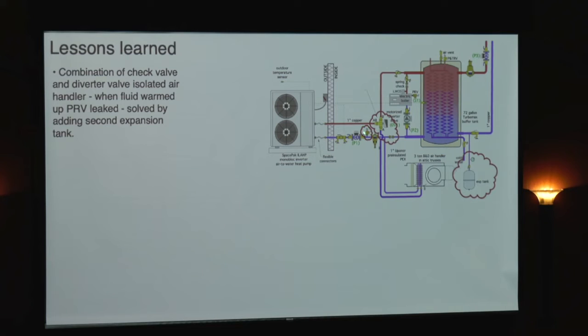The relief valve is here. And what happened? Well, we sealed off all communication, so to speak, was broken with the expansion tank. And just that chilled fluid warming from maybe 45 degrees up to maybe 70 degrees, that was enough expansion to cause the relief valve, it didn't burst open and shoot a geyser of fluid out, but it would just start dripping. And so it's one of these duh moments, right?